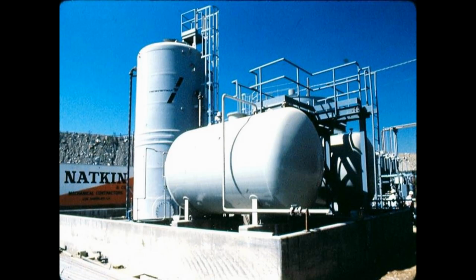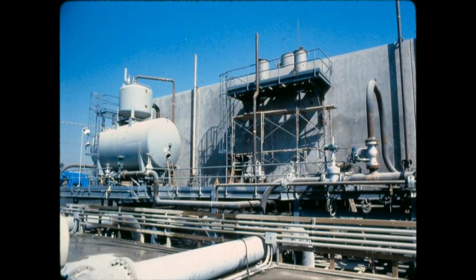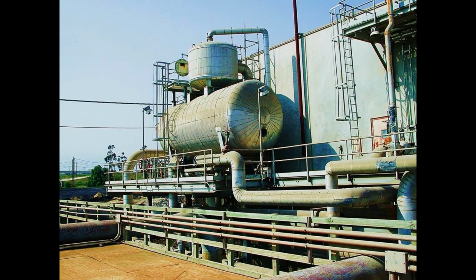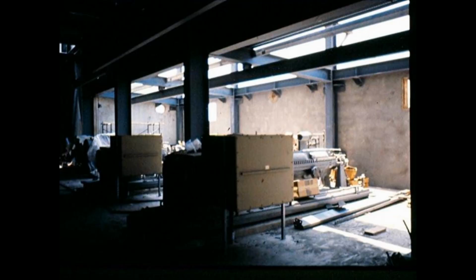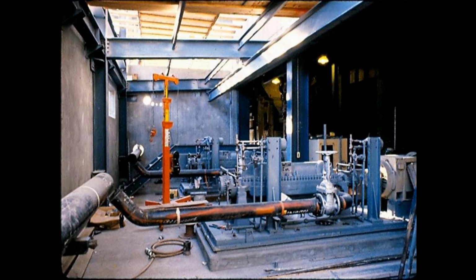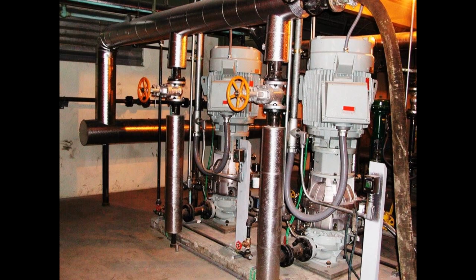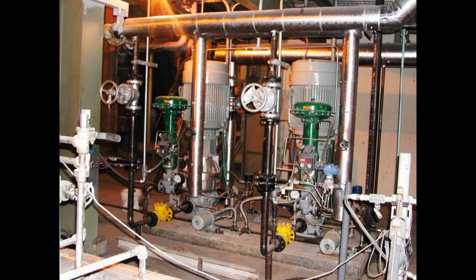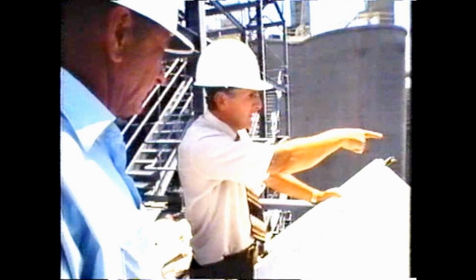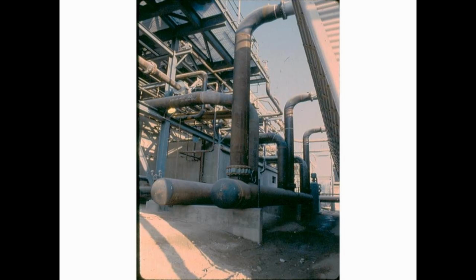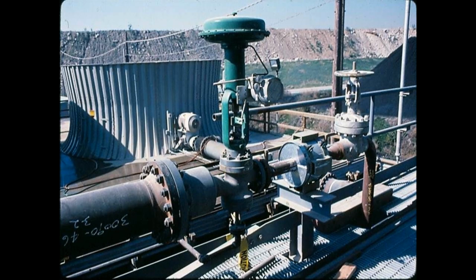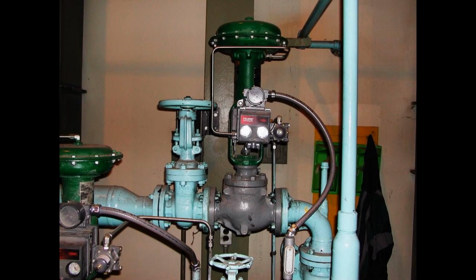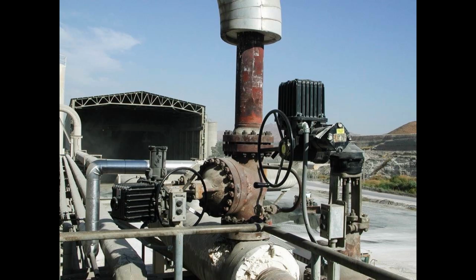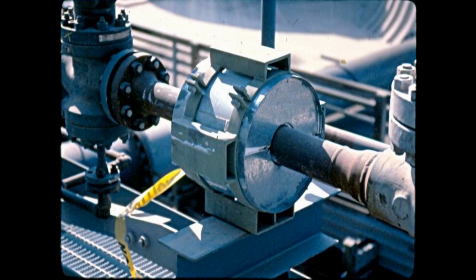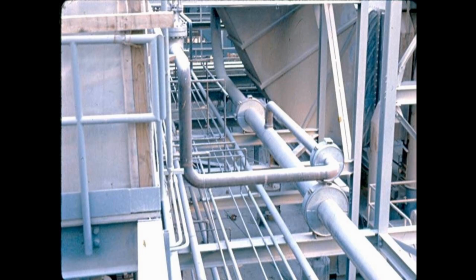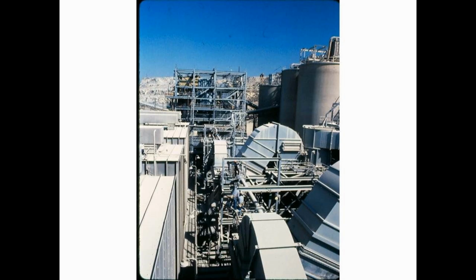demineralized water surge tank with transfer pumps provides water in the event the plant water system is disrupted. Entrained air in the condensate is removed in the deaerator vessel. An oxygen scavenger is injected into the storage area to polish off any traces of oxygen. A neutralizing agent and corrosion inhibitor are injected into the boiler feed water downstream of the takeoff to the attemperators. Wastewater containing environmentally benign solids and chemicals from the cogeneration facility, such as cooling tower and boiler discharge, will be reused in the present cement plant dust slurry process and therefore does not represent a waste disposal problem.